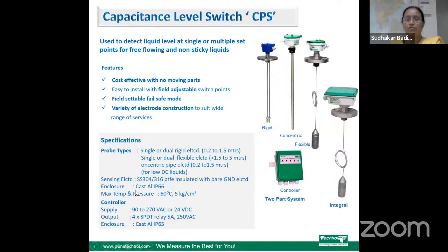Then the enclosure of this switch will be IP66, and the switch is suitable for 60 degrees Celsius and 5 kg per centimeter square. Supply will be 90 to 270 volt AC or 24 volt DC, and as the output of this switch you will get relay contacts with 5 ampere at 250 volt AC rating. So here you can see the rigid construction, then concentric construction electrode for oil application, then flexible electrode for longer ranges, and this is the switch with integral controller.